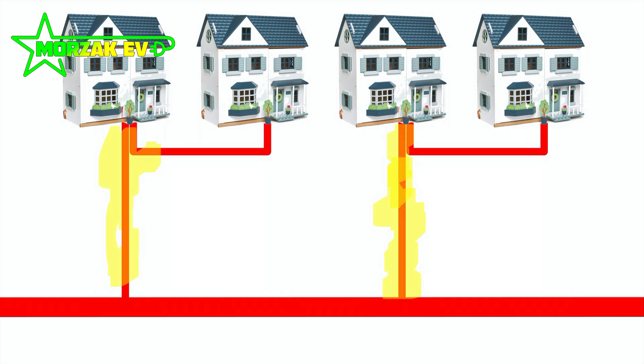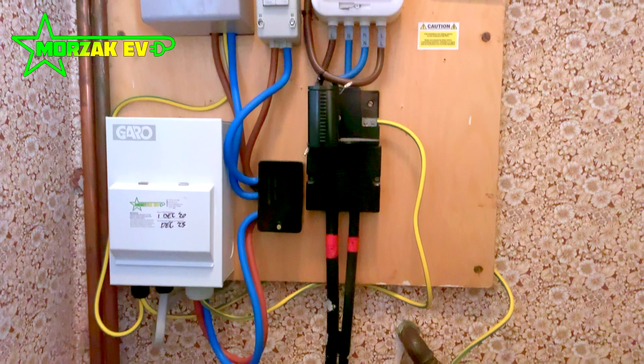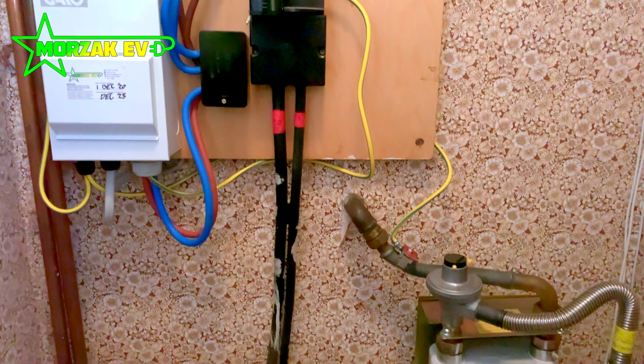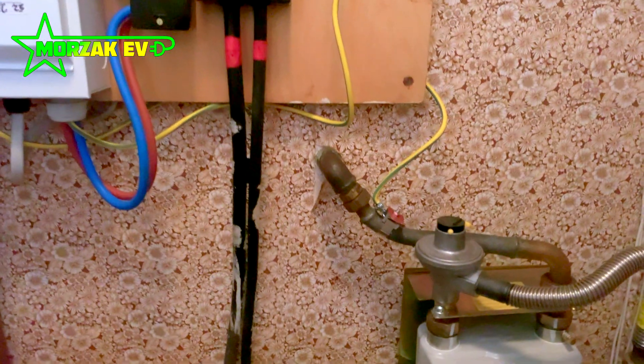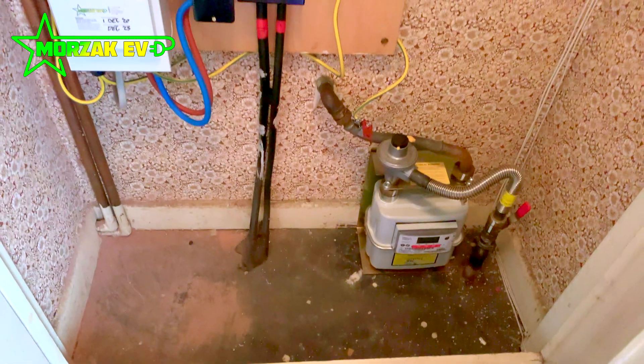They're kind of a sleeping time bomb on some houses. Your fuse might be a 60 amp fuse serving two houses, but with house electrics being upgraded, you could be pulling up to 80 amps in each house. When electricians do work, they should be checking this and getting the fuse checked out and upgraded if necessary. However, this isn't really general practice. Most electricians will look at the mains fuse and assume it's 100 amps because it says 100 amps on it.